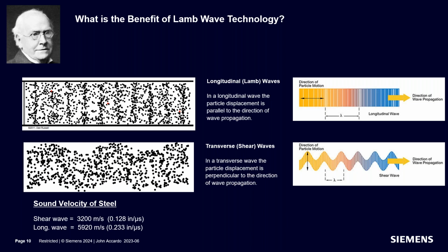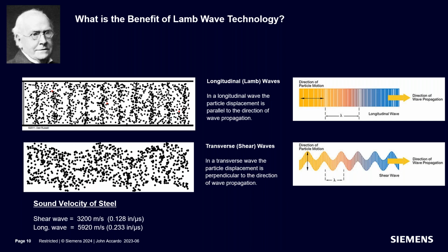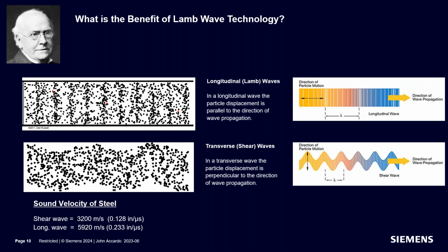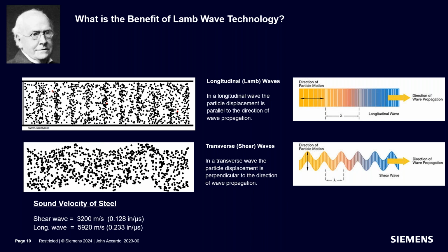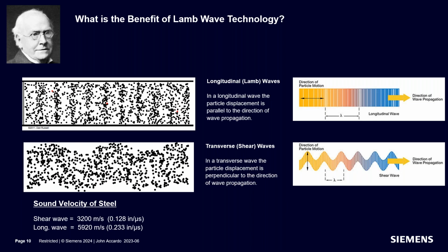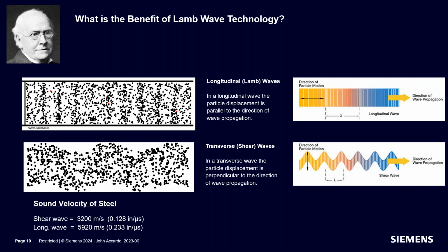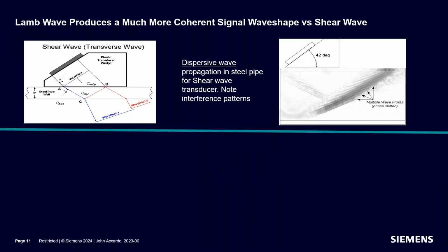Also, if we look at the sound velocities down at the bottom of the screen there, you'll see that the longitudinal wave travels a lot faster than the shear wave does down the pipe because of the method that it utilizes. So let's see what that benefit is. If we look at a shear wave at the top of the screen here, you see the outline of the transducer, and you see the beam angle that's traveling into the pipe. And then there's a refraction that takes place, but it does not turn to the 90. It refracts and then it starts rattling its way down the pipe wall. So it's bouncing down the pipe wall.